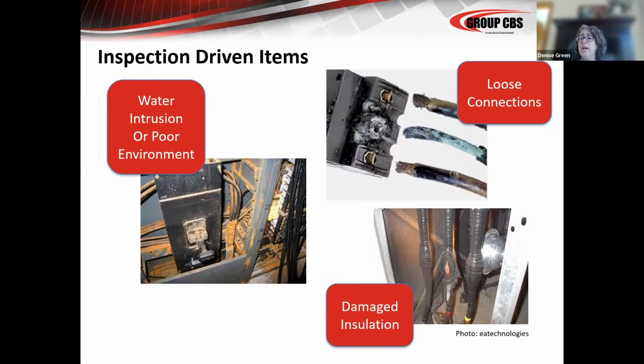The lower picture is damaged insulation. Obviously, your substructure and inspection of your substructure goes hand in hand with your circuit breaker maintenance. So taking the time to take outages on a regular basis, so that you can inspect the structure as well as your breakers, can help prevent an arc flash situation. So the maintenance goes to not just the breakers, but your substructure as well.